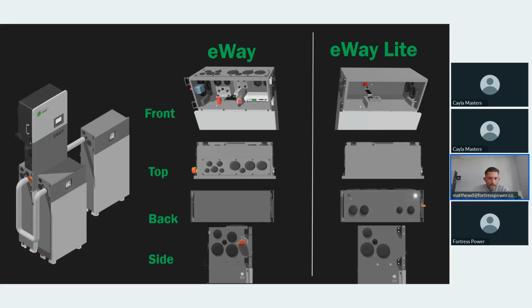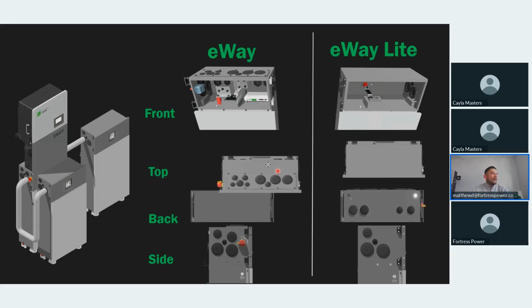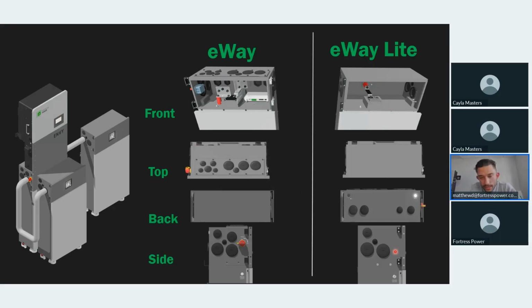It has a 750 amp bus bar, as I mentioned before, and the E-way Lite has a 250 amp bus bar. So it's perfect to just pair it to this bus bar if you were to install it on the side or on the front, as you see in the picture. I made an oopsie here. This actually is inverted. Here we go. Sorry, my apologies. The E-way Lite would not include that top compartment. I apologize, I have to flip this. There you go. Basically, this is swapped. So the traditional E-way will include the back knockouts with a status indicator, and the E-way Lite would not. That's essentially what I was trying to get at.